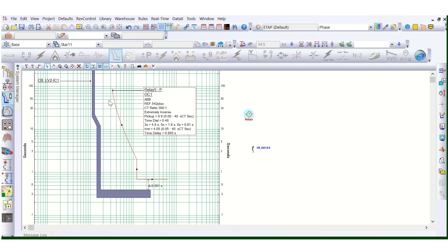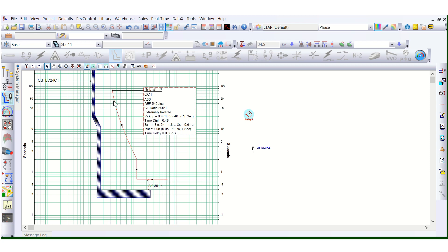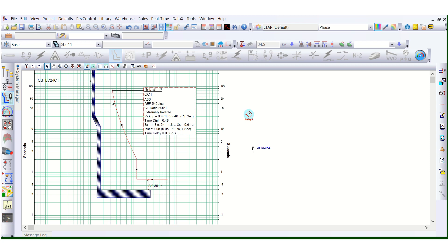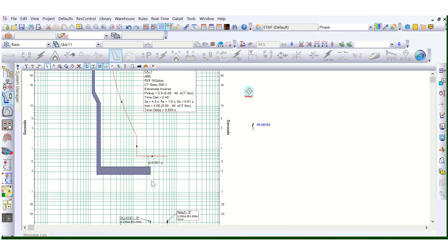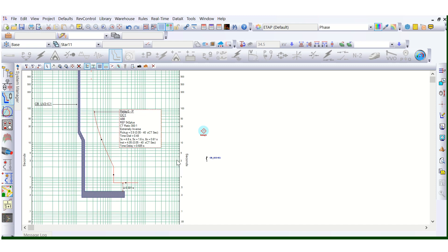For overcurrent, when the relay will give the trip command to the circuit breaker depends on the fault current — the relationship is inverse. More continuous or overload current means less time, and less current means more time to provide the trip command. This follows the inverse characteristic for overcurrent or overload protection. For instantaneous protection, the relay will give the trip command instantaneously — there should be no intentional time delay. This is the basic difference between 51 and 50 elements in any IDMT relay.